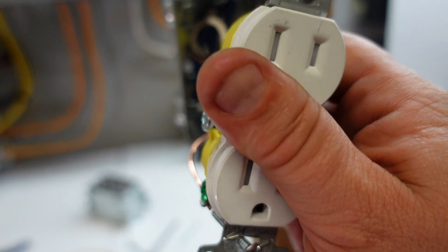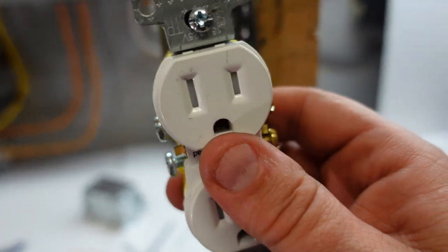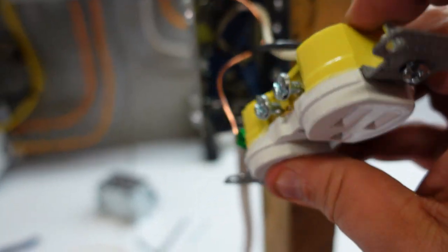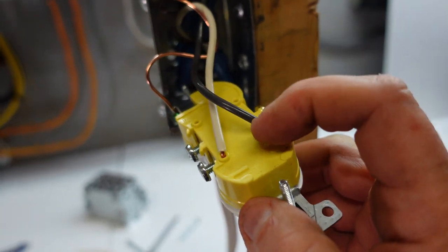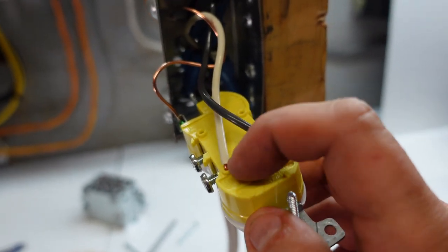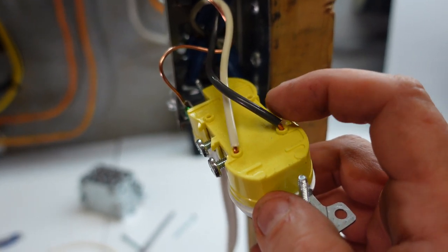These will work fine with small LED loads that are plugged in, but if you load this receptacle up rated for 15 amps of any kind, then the two little pin connectors that are in the back here will not support that and end up burning the receptacle.